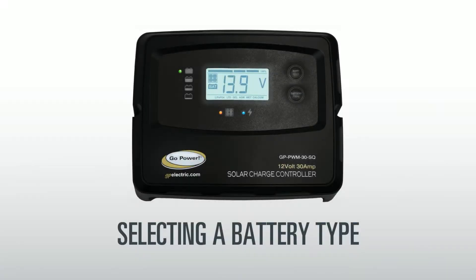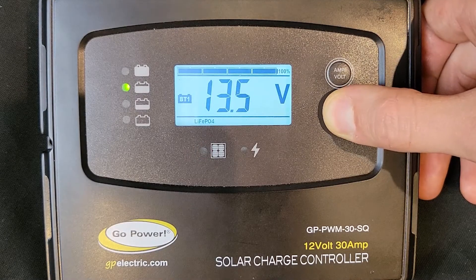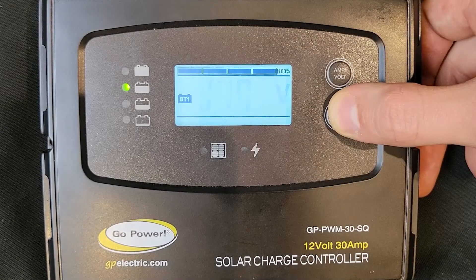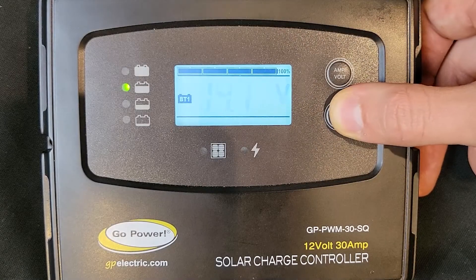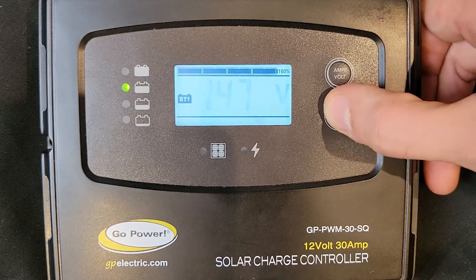Selecting a battery type: To select your battery type, hold down the battery type button for 3 seconds. Release the button when the display shows blinking digits. The controller has 6 charging profiles: lithium, LTO, GEL, AGM, wet, and calcium.